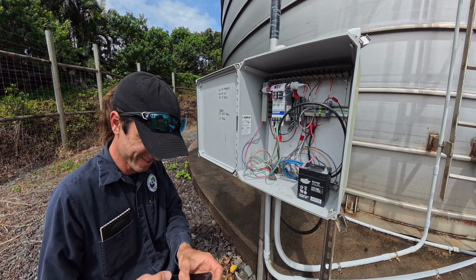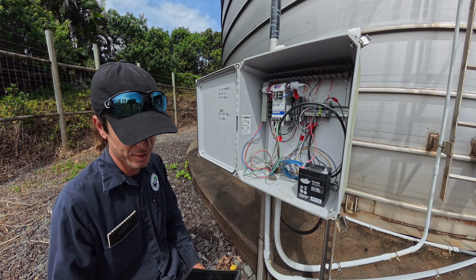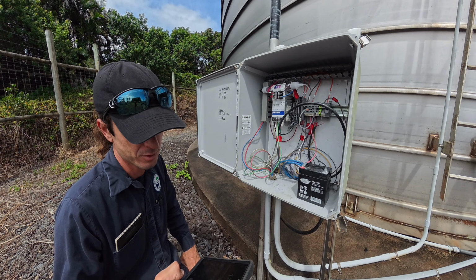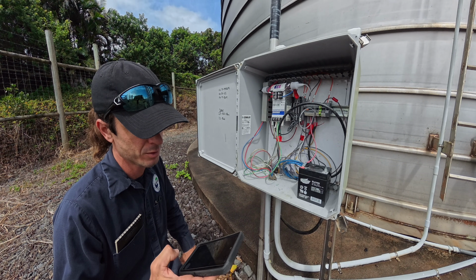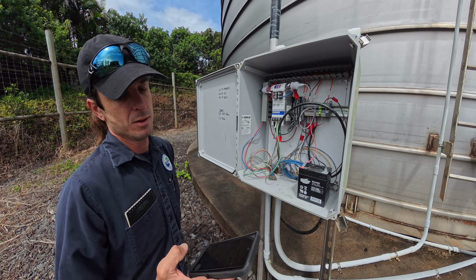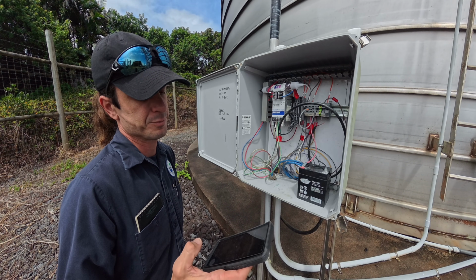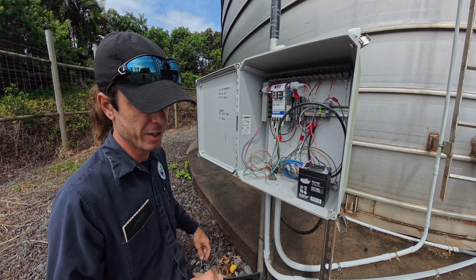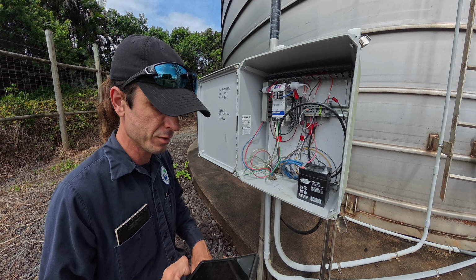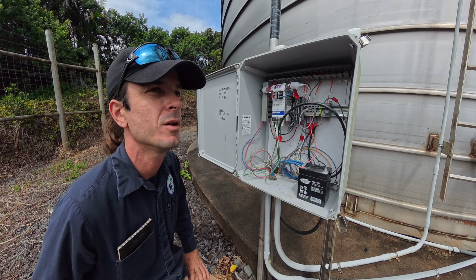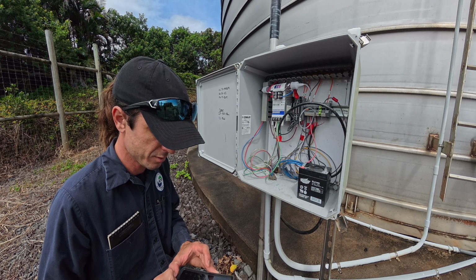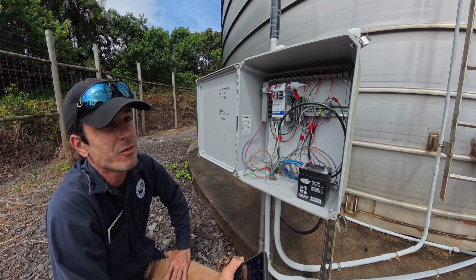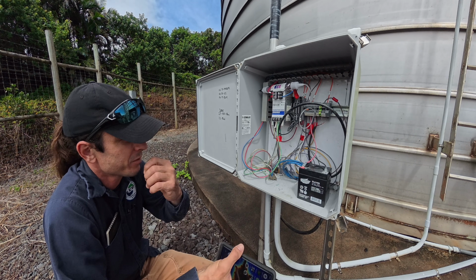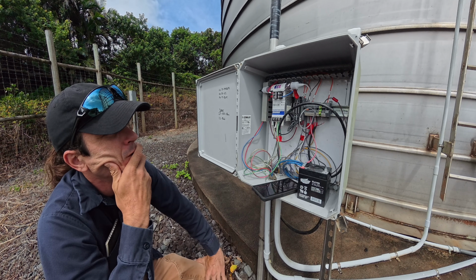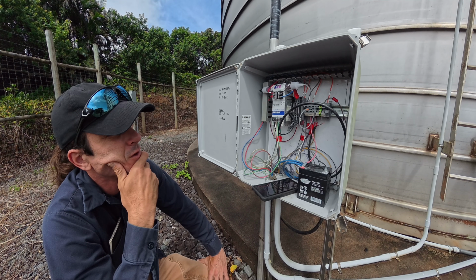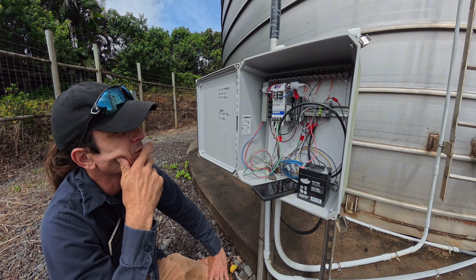It's in there somewhere. So we've got 12 volts DC divided by 169 ohms. That is 0.071 amps. Man, that is not good. Tens, hundredths, so 7/100th of an amp. We were on an 8th amp fuse. It shouldn't have really popped it. Maybe with the milliamps. Yeah, so 0.071 is 71 milliamps on our 4 to 20 milliamp circuit. So that'll definitely pop that fuse. We could try it again and see if it pops it.